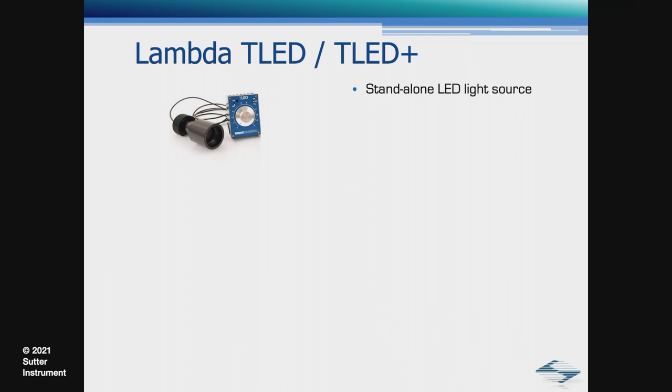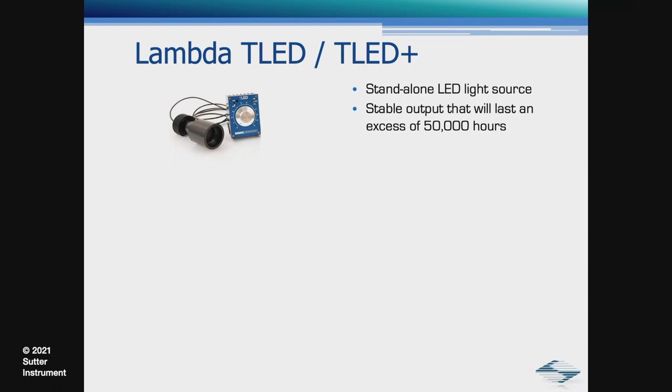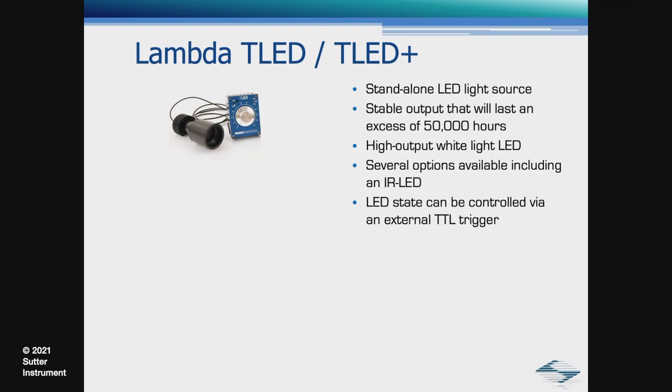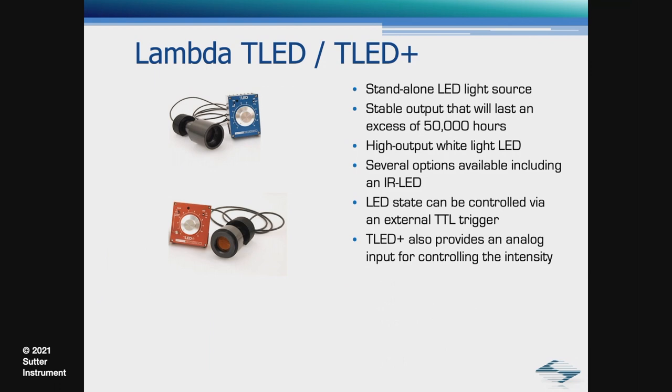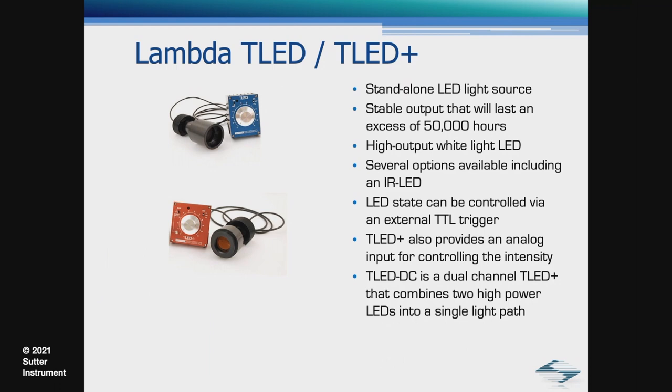Next is the transmitted light source, powered by a Lambda TLED. The TLED is a standalone LED light source, has stable output that will last an excess of 50,000 hours, has a high-output white light LED. Several options available, including an IR LED. The LED state can be controlled via an external TTL trigger. The TLED Plus also provides an analog input for controlling the intensity. We also have a TLED DC, which is a dual-channel TLED Plus.